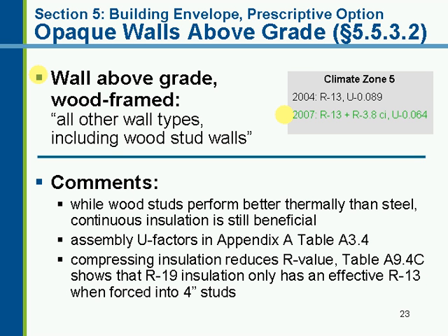Now, we all know that wood studs perform better than metal studs, but wood has an R value of about 1.25 per inch, and fiberglass, for example, has an R value of, say, 3 or 3.3 or 3.5 per inch. So you see that the insulation is still performing 3 times better than the wood stud itself. So the wood, in effect, is a thermal bridge there. So this is a way to minimize that even for the wood assemblies.